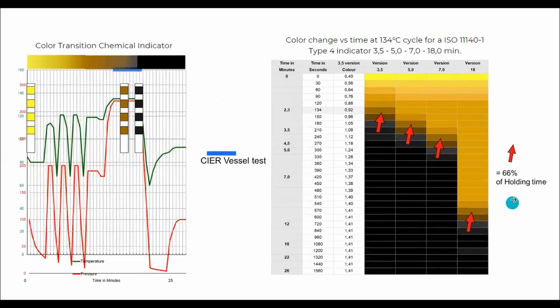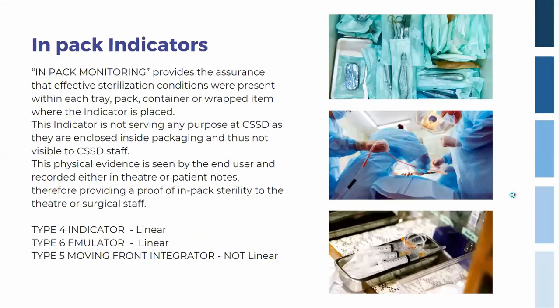Thank you, Shane. So I'm going to continue with in-pack indicators. They consist of the type 4 short indicator, which is a linear test, the type 4 long indicator, which is also linear, the type 5 moving front integrator, which is not a linear test, and then the type 6 emulator indicator, which is also linear. In-pack monitoring provides the assurance that effective sterilization conditions were present within each pack, tray, container, or wrapped item where the indicator might be placed.